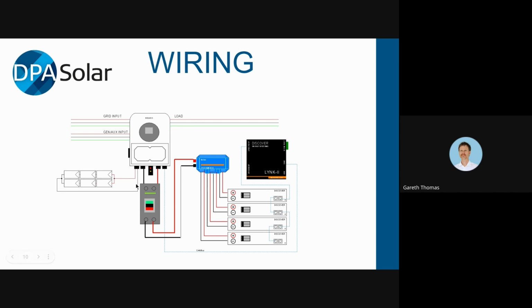It's got a PV input. Different models have different numbers of MPPT trackers. They have MC4 connections on the outside of the inverter. And then it has 3 AC connections. It has a grid input. It has a load or an output, if you like. And then it has a generator or auxiliary AC input as well.